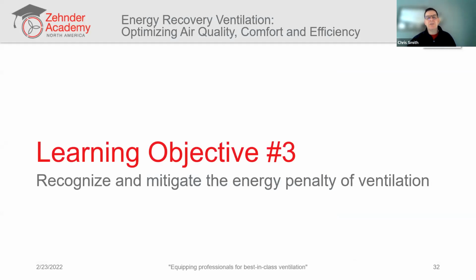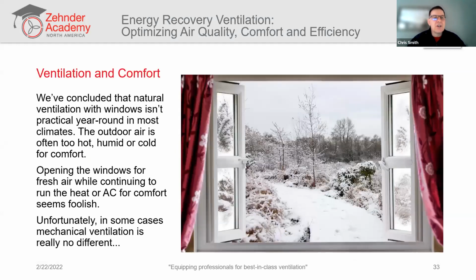But let's talk about the energy penalty. Learning objective number 3 is recognizing and mitigating the energy penalty of ventilation. We've recognized that window ventilation, while easy and effective, is not really practical year-round in most climates. The outdoor air is often too hot, humid, or cold to be comfortable. If we open the windows to get fresh air, we're going to continue to run the heat or air conditioning to get the proper level of comfort inside the house. That's kind of foolish, to open the window just to run our conditioning systems more.